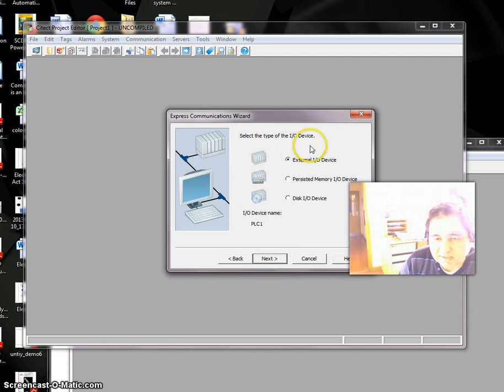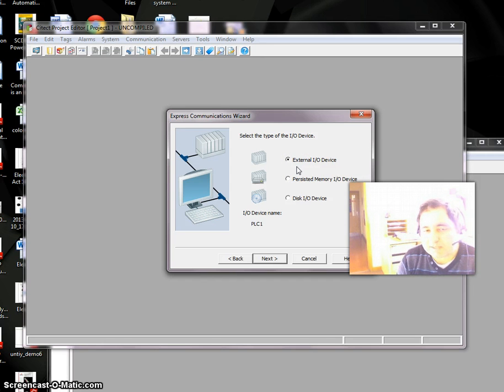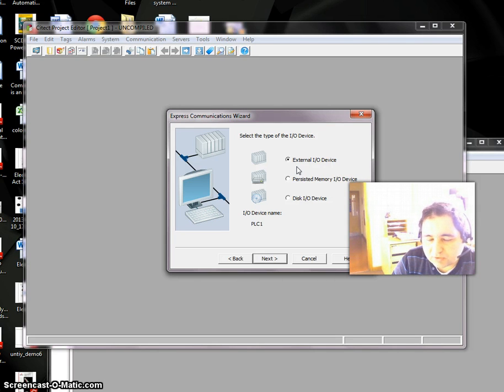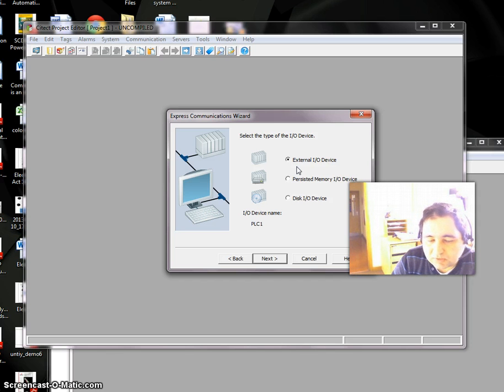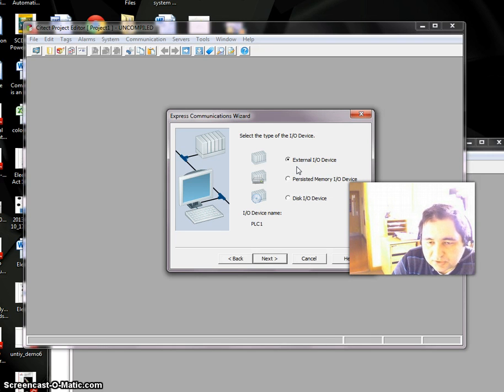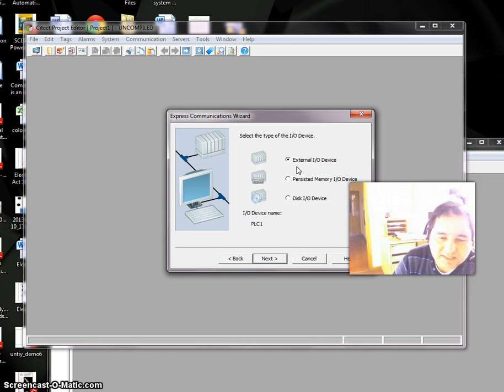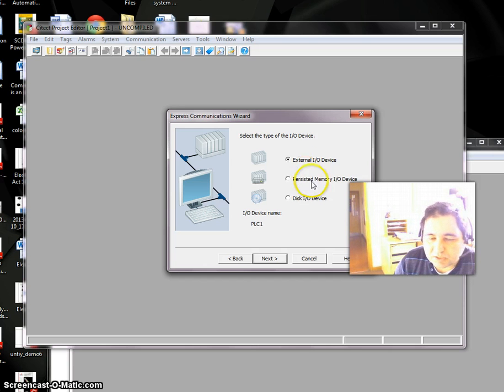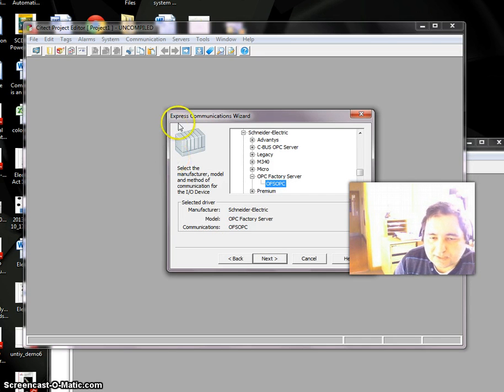Here we have to select our type of IO device. We can have three types. External IO Device means the PLC is already connected. Persistent Memory IO Device means the PLC is not connected right now but you want to use simulation. Disk IO means the information comes from a file or disk, not from an external source.